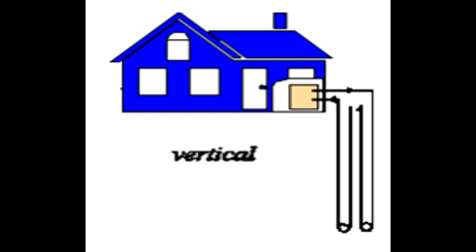Now the second connection I talked about earlier is the closed loop geothermal loop fields, and the type we install, that are approved, is vertical, where we drill holes anywhere between 200 and 500 foot deep, run the U-bend down and back up, grout the hole solid, and run it into the heat pump. Those are probably the most common on large commercial projects because of lack of land.